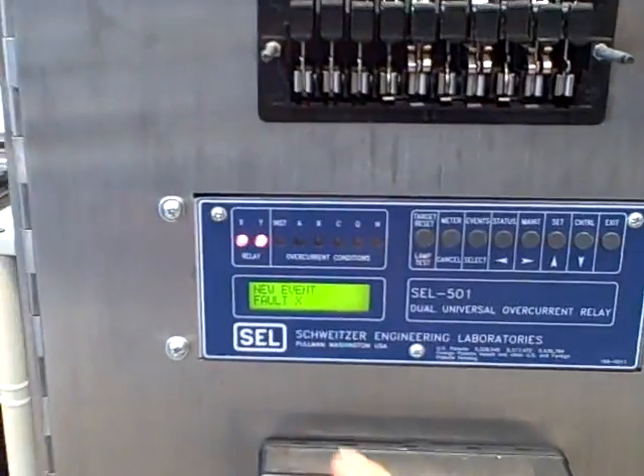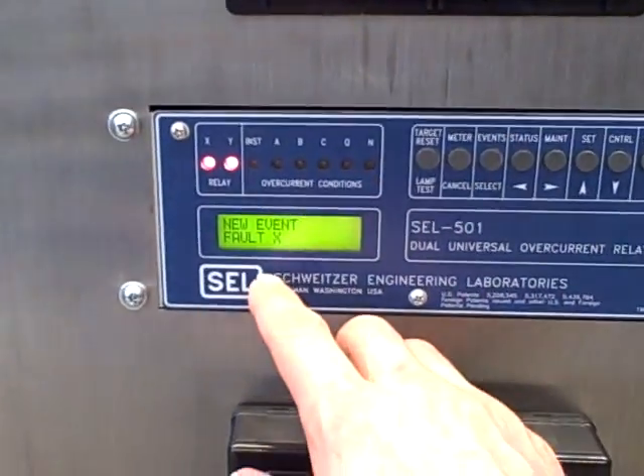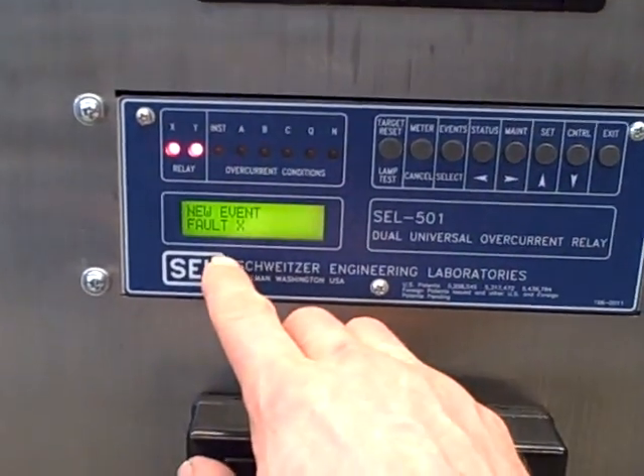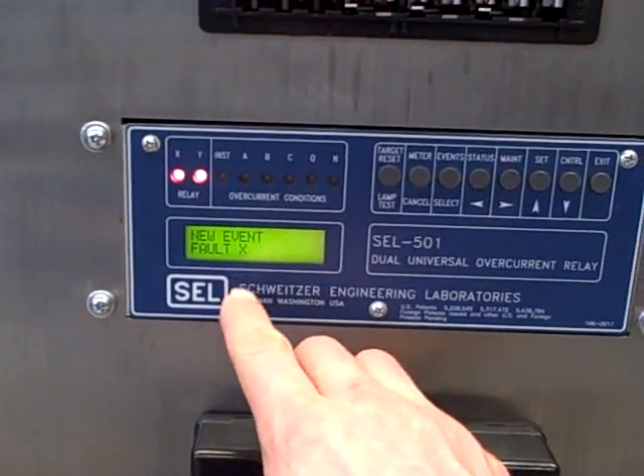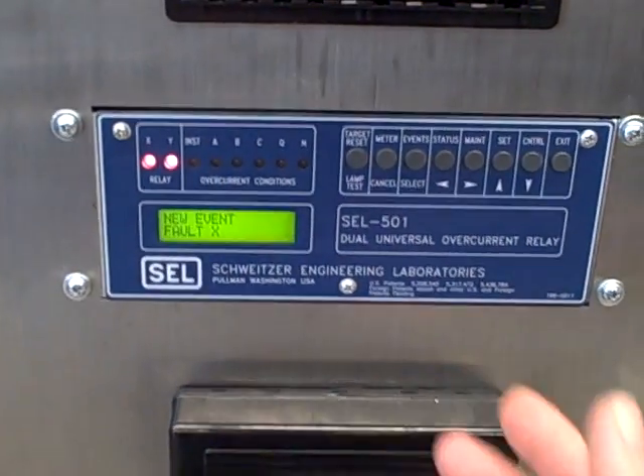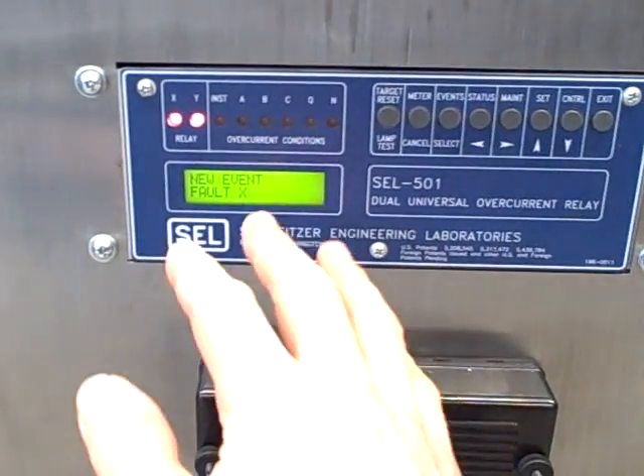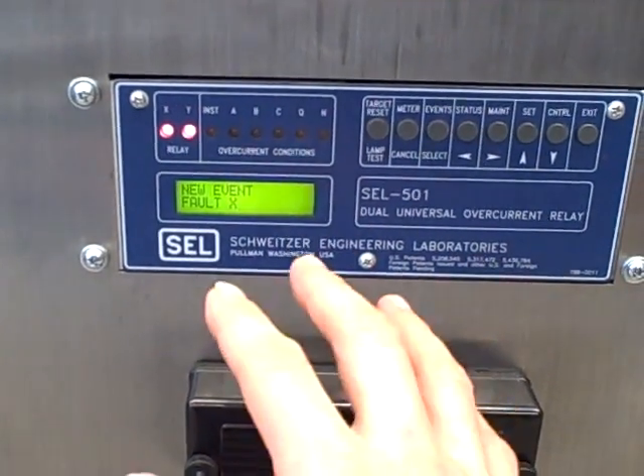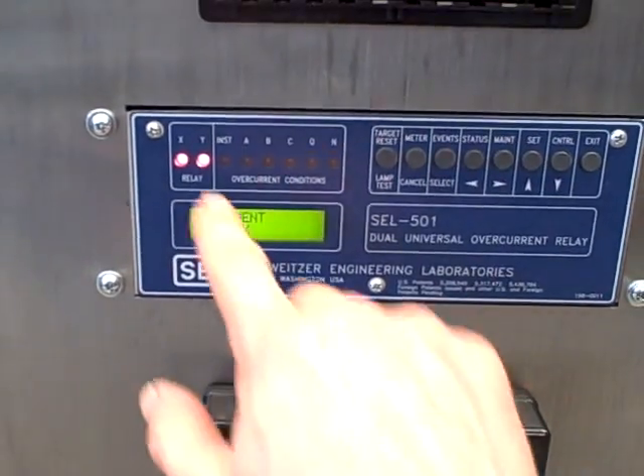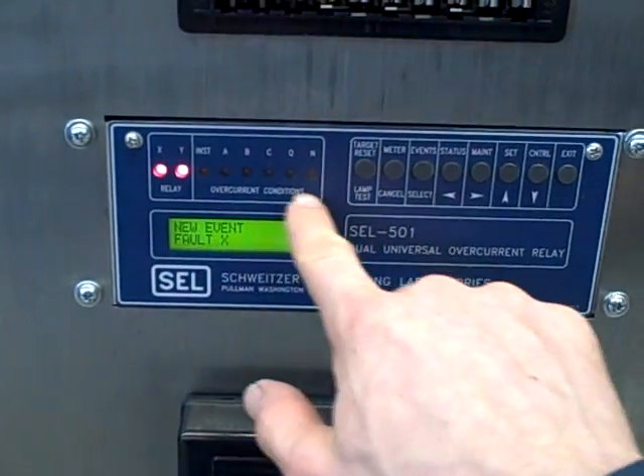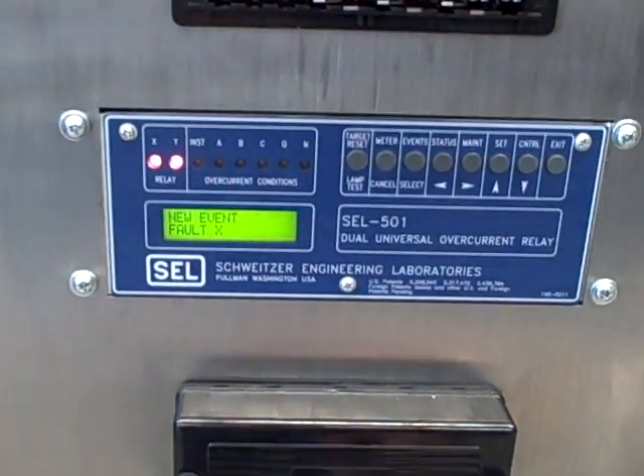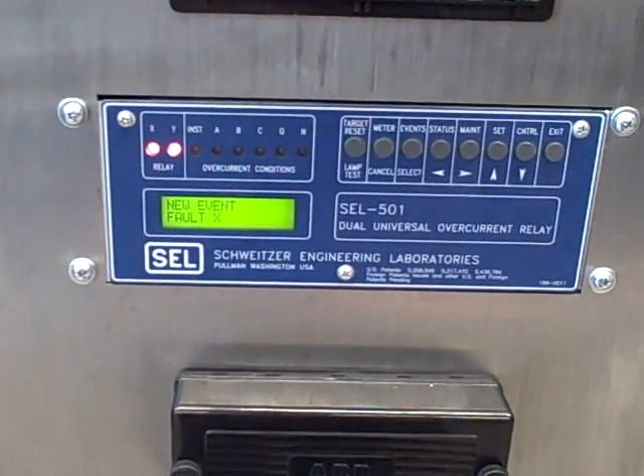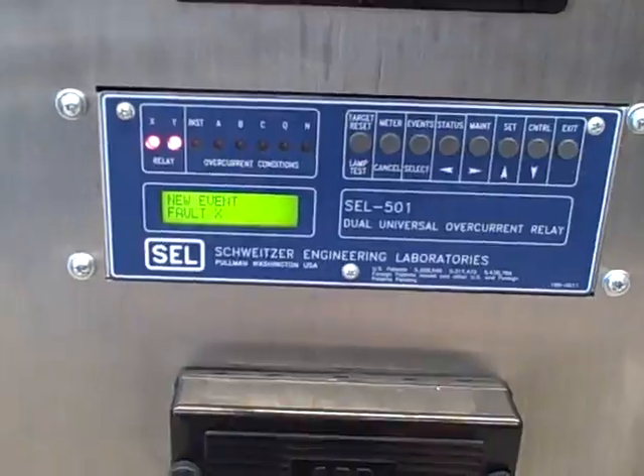And indeed the vacuum cleaner did not trip. If we come over here on the relay display, we see something that says New Event Fault X. It doesn't give us any more information than that on the front display. We can see there's no targets actually set here, no trip took place. So it's kind of curious what happened.